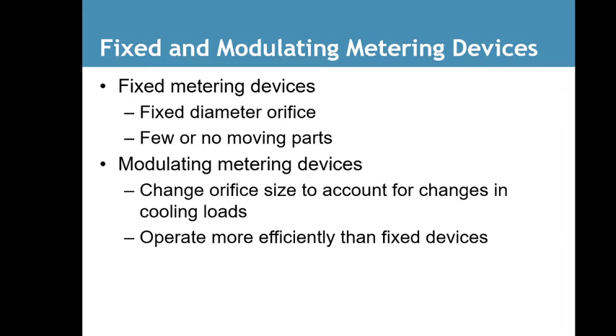All the units that I've installed in the past, if I needed a metering device, which was a fixed orifice type, all you have to do is go to the supply house and ask them for one. They give it to you. They have many of these things, and they're very inexpensive to manufacture, and they want your unit to run the best it can. So they really don't charge you for these. You could just ask for one. And they come in all different sizes. The good thing about these, there's few or no moving parts. They do have filters and screens before them so they don't get clogged.